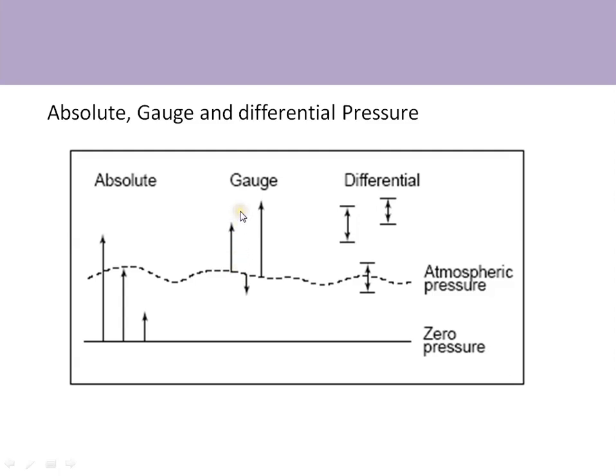If you want to measure pressure at two different points, differential pressure is used. One common application is the orifice plate — across the orifice we measure the pressure drop, and that pressure drop is proportional to the flow rate, so differential pressure is measured in that case.